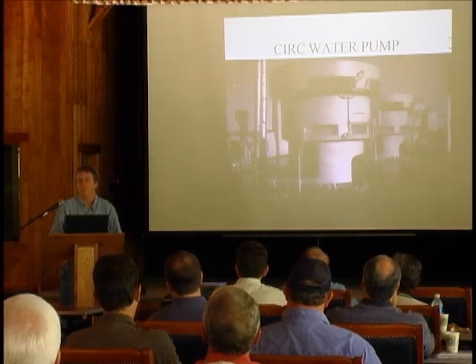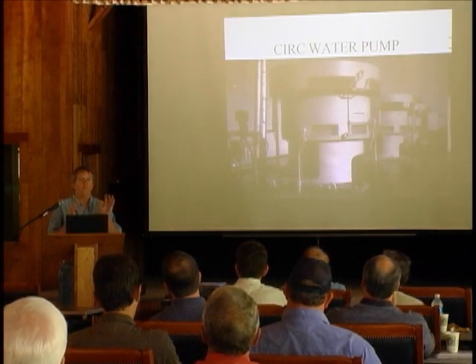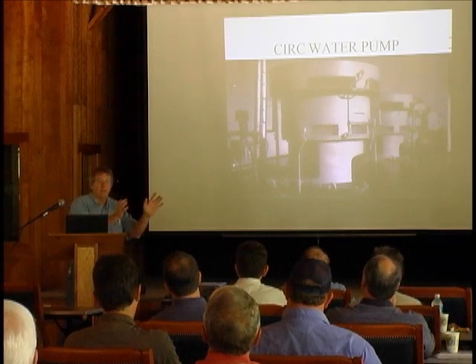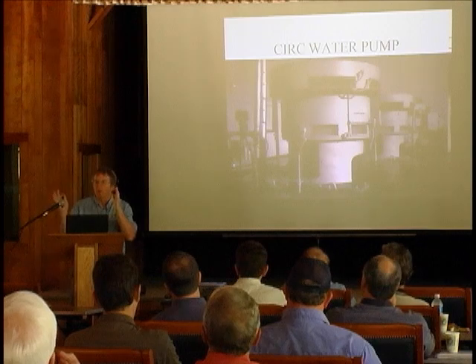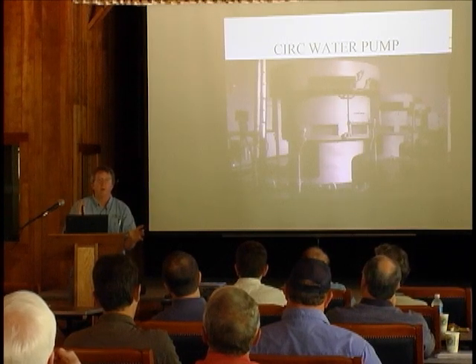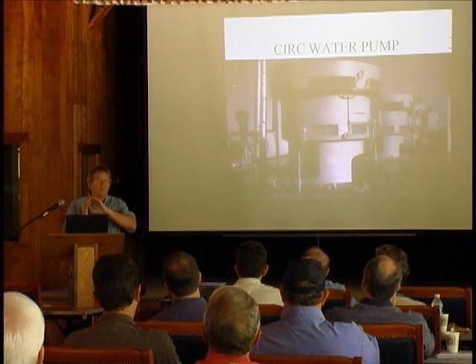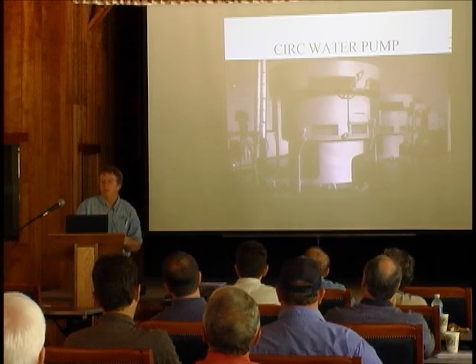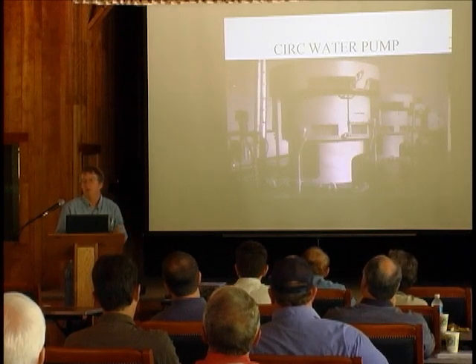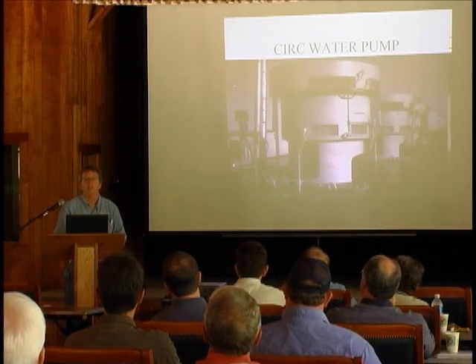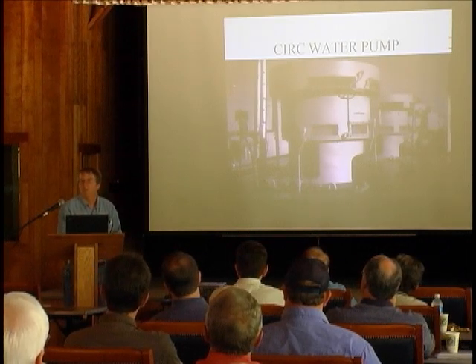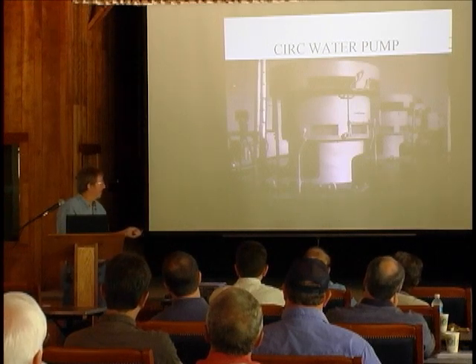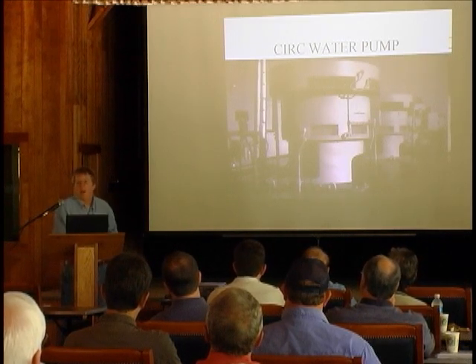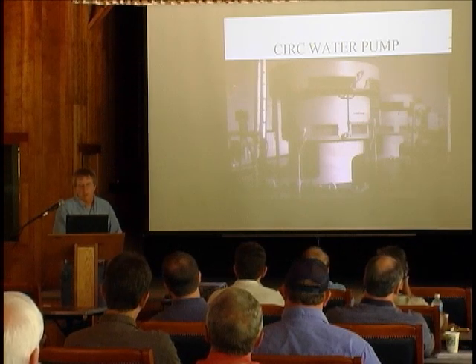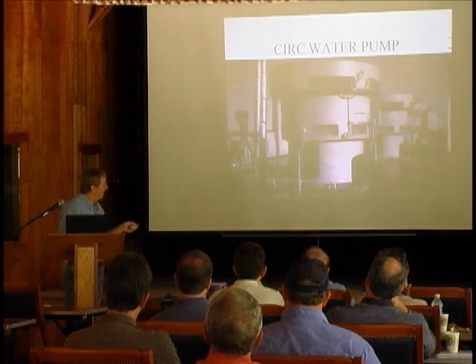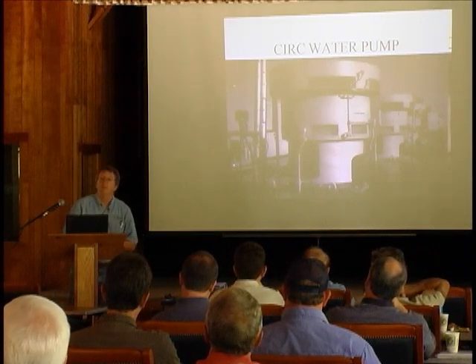The problem was the system wasn't designed that way. If I have 2 pumps pumping in a header, I'm going to create a certain amount of back pressure, and the pumps are sitting right comfortable where they want to be. If I shut 1 pump off, then that 1 pump's operating against lower back pressure, and it's flowing like crazy. It was just eating the impellers up, like metal-eating termites, and the pumps were failing left and right. It was all well-intentioned to try to save some energy, but in reality it was creating reliability problems. So that's a case where we've got a pump operating against not enough head.